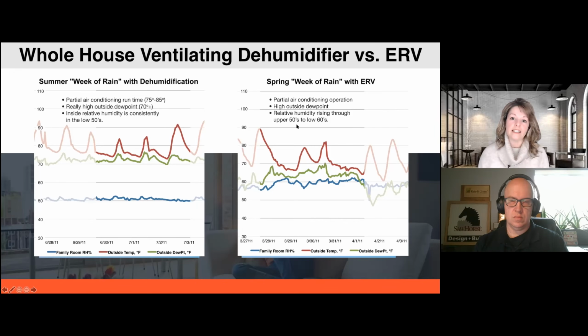So what we did is we removed the ERV and put in a whole house ventilating dehumidifier. Again, we got the partial AC run times, extremely high dew points going on outside here. But we just installed the dehumidifier and set it to 52%, 50% ish. And the dehumidifier is just going to focus on keeping that relative humidity to that set point. So we're not concerned about what the dew points are outside. We're going to focus on keeping that RH inside to where we set it.